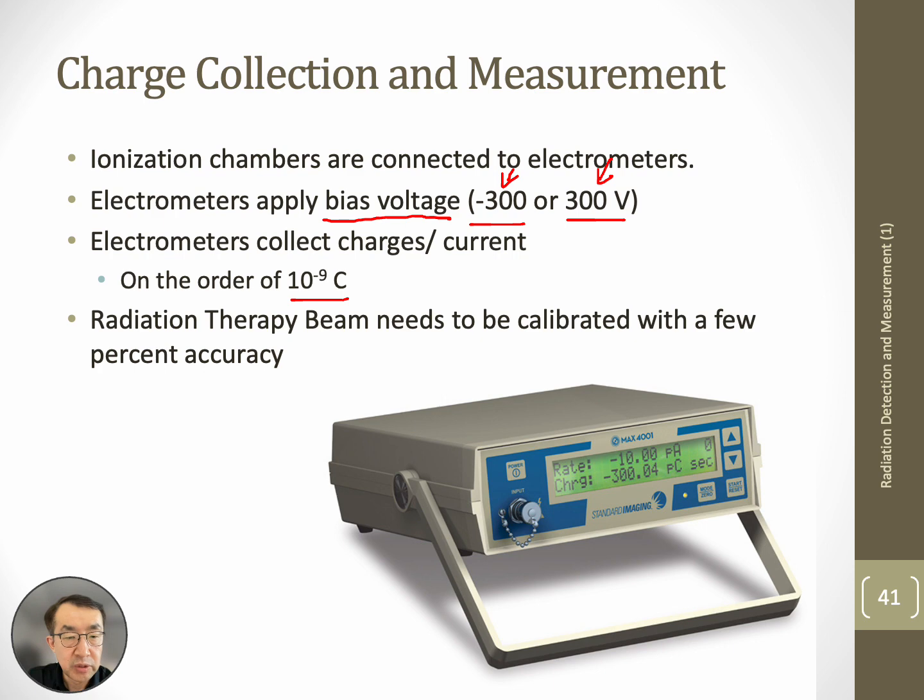Okay, so what do we do with this device? We connect this to the thimble chamber or well ion chamber, and this device itself needs to be recalibrated every 2 years, along with those ion chambers that I mentioned earlier. Especially the Farmer type chamber or well ion chamber that we use, we send this with the electrometer to an accredited calibration lab in Wisconsin every 2 years.